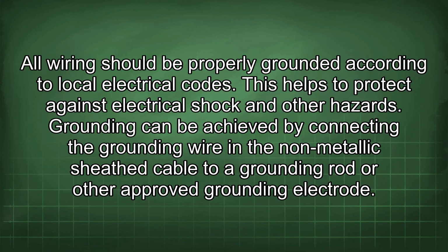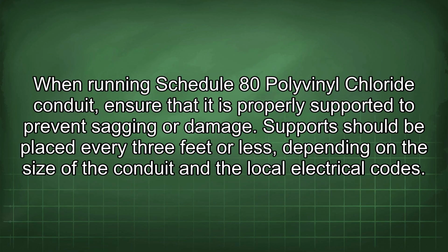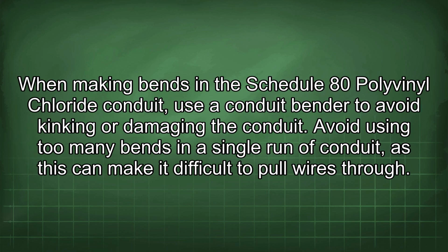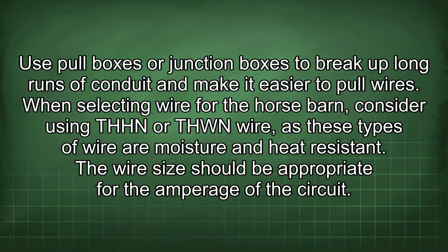approved grounding electrode. When running Schedule 80 polyvinyl chloride conduit, ensure that it is properly supported to prevent sagging or damage. Support should be placed every 3 feet or less, depending on the size of the conduit and the local electrical codes. When making bends in the Schedule 80 polyvinyl chloride conduit, use a conduit bender to avoid kinking or damaging the conduit. Avoid using too many bends in a single run of conduit, as this can make it difficult to pull wires through.